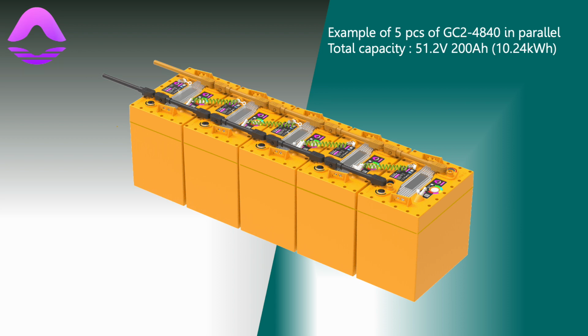A notable feature of the GC2-4840 battery is its true parallel connection capability. Up to 15 units of GC2-4840 can be cascaded in parallel to provide up to 600 amp-hours, or 30 kilowatt-hours, of energy. Simultaneous charge and discharge of this battery bank is allowed, thanks to the built-in BMS safeguarding these operations.